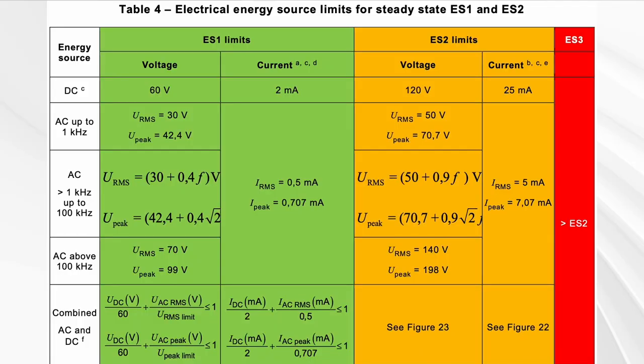To know what the limits are for voltage and current, it depends on the frequency, whether it's DC or AC, and so on. For example, the simplest case: if it's DC current, no higher than 60 volts and no higher than 2 milliamps, it's ES1. If it gets higher on any one of these dimensions, it becomes ES2, and higher still, ES3. This covers a long table.